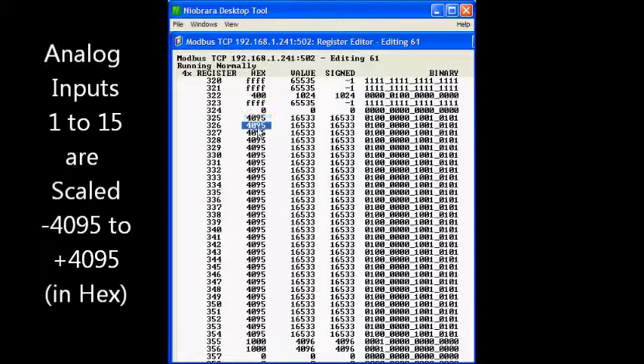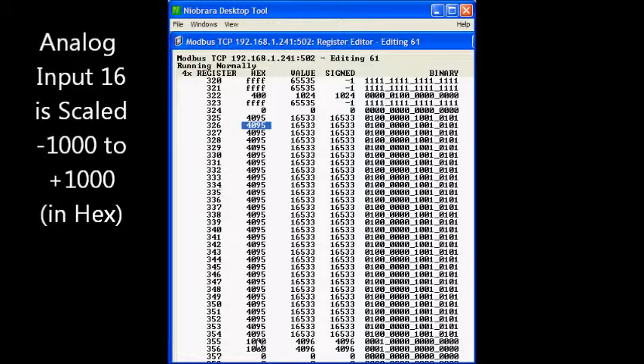Inputs 1 through 15 are set for plus and minus 4095 so that a 0 to 10 volt input gives a reading of 0 to 4095.